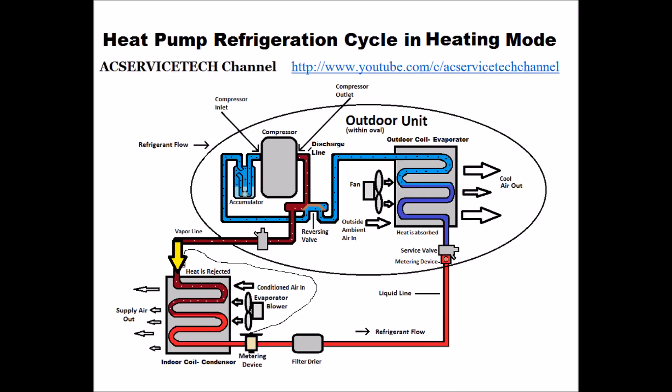It used to be called the evaporator coil, but now it's called the condenser coil because we're in heat mode. It comes into the condenser coil as a high pressure, high temperature vapor refrigerant and it starts rejecting heat into the conditioned air. As it rejects heat, it lowers in temperature until it gets to the saturated state where liquid and vapor both exist. It then goes through the saturated state, which is where it's rejecting most of its heat.